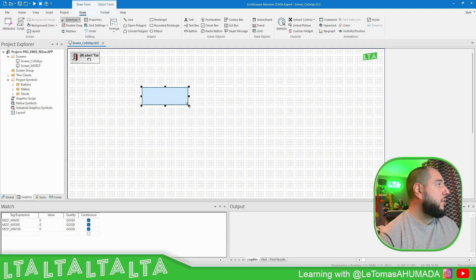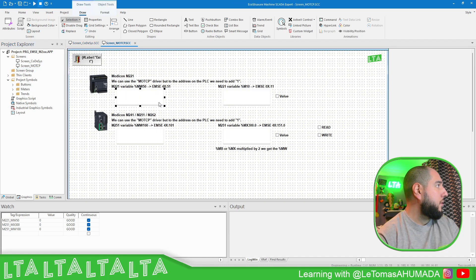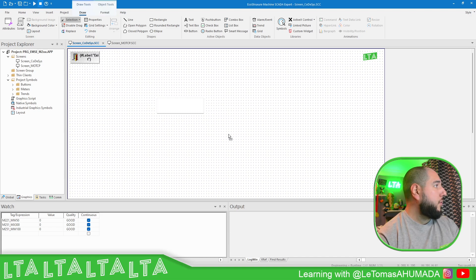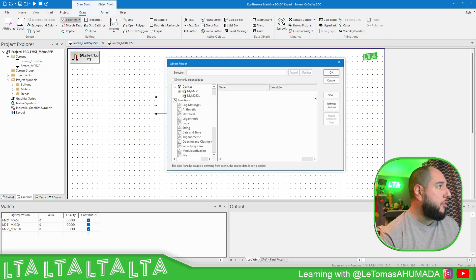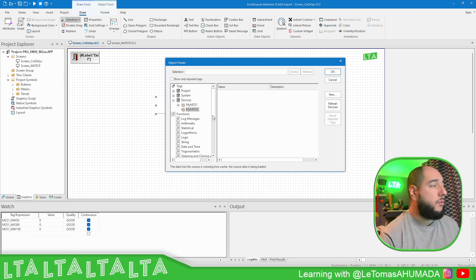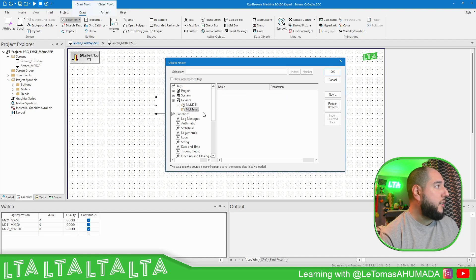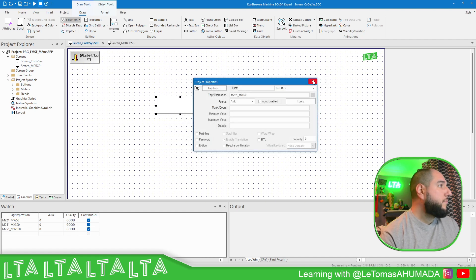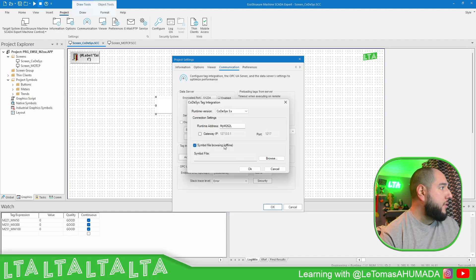Let me just copy one element that I have on the old screen that I was playing with — I just don't remember which option I was using. Okay, there we go, I copied this in here. Now double-click and I'm going to select the new tag expression. You should be able to see here in Devices the M262 that you have. If you try to log in and refresh, it will take some time and may not see anything — at least I wasn't able to see that in my case. So in order to avoid that, go to Check Communication, select the target, Configure, and select Offline.